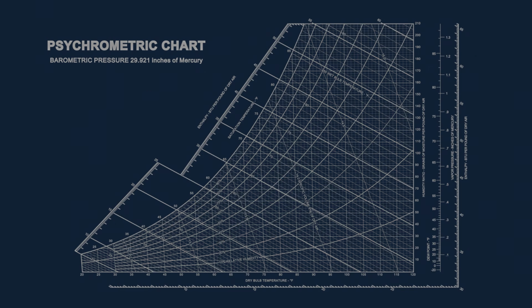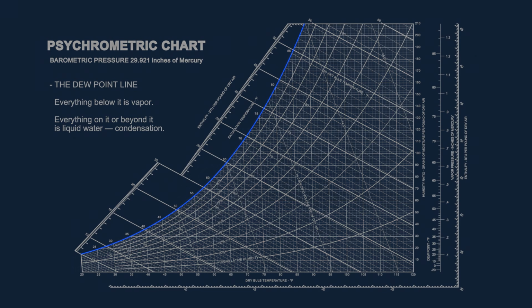Now let's talk about my favorite, what I call the real boss of comfort, the dew point line. On the chart, it's the saturated curve running along the left edge. Everything below it is vapor. Everything on it or beyond it is liquid water, otherwise known as condensation in this case. Cross that line and things start sweating. Or in the case of weather, clouds form. Your coil, your ductwork, your windows, all of it obeys that curve.